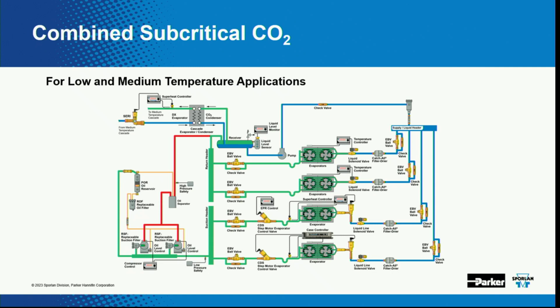Has anybody experienced a board failure due to a valve failure? Is that on the 6, 7, 8? So is it shorting out in the valve, and that's causing the board to somehow short? So the valve shorts out, and in our setup, it's refrigeration, but it goes back to a Dixell, and it shorts out the Dixell, then it kills the comm loop. Exactly, it drops out and hits all the way back to the main board.